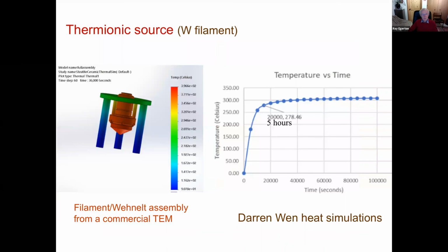Now, we wanted to start off with a thermionic electron source, just a heated filament. And so the idea was to take a commercial thermionic source. We don't want to reinvent the wheel when it's not necessary. And so we thought that at least we will be guaranteed of an electron beam without any problems. There were, in fact, problems, in the form of wires inside the microscope melting after a period of hours.